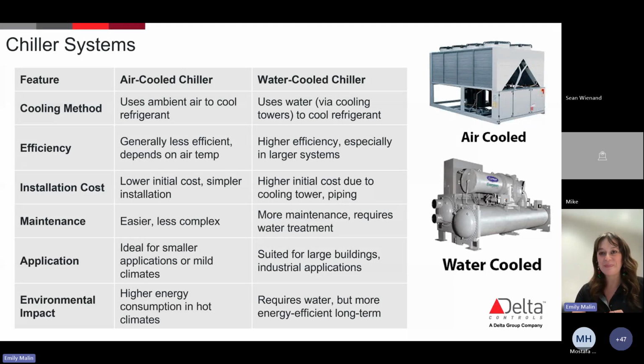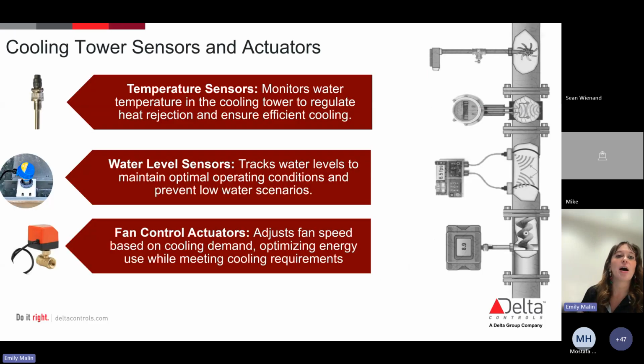occupant comfort, right? So within our chillers, sensors and actuators, so our sensor network within chillers, basically, we're going to have a few things, again, very similar to before. We're going to have our temperature sensors. This is just what is monitoring the water in that heat rejection cycle, in order to monitor the temperature both in the cooling tower as well as on the water level itself. Your water level sensors, this is just going to track levels and maintain optimal operating conditions. Essentially, all this is doing is preventing low water scenarios. And then we saw this again, fan control actuators.